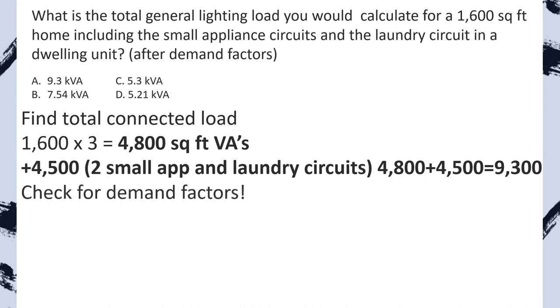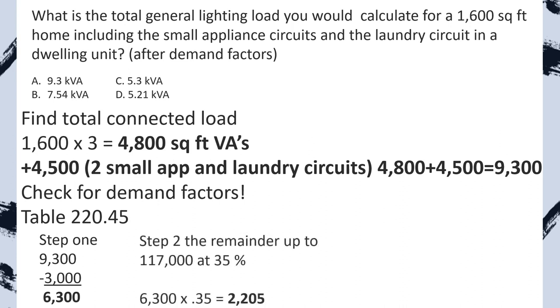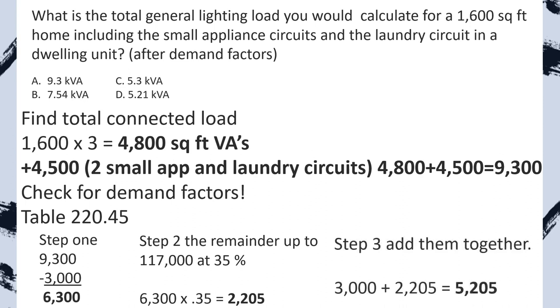Now we check for demand factors. We head over to table 220.45, and step one, we're going to set 3,000 to the side because we take 3,000 at 100%. In step two, we're going to take that remainder and multiply it by 0.35. Then we total those two back together, and we select D. Great job.